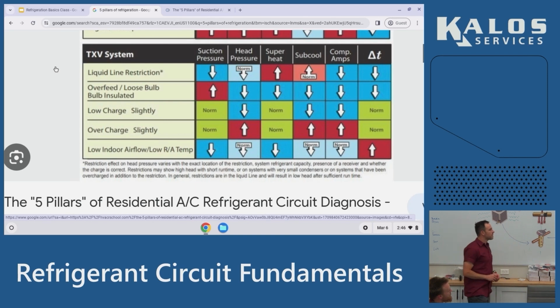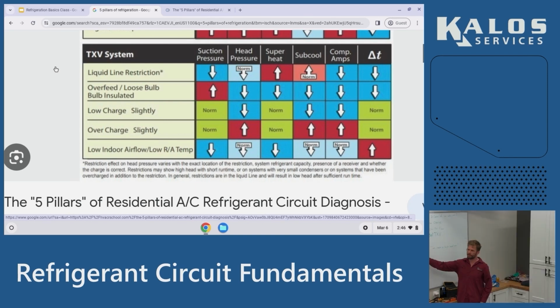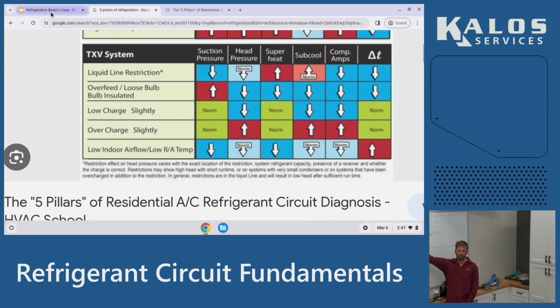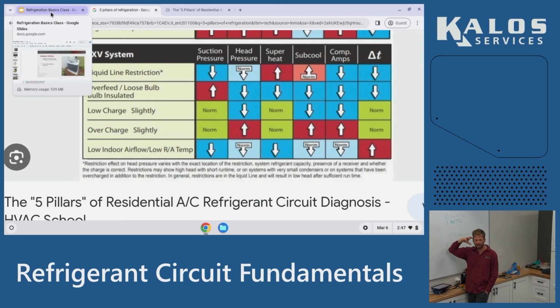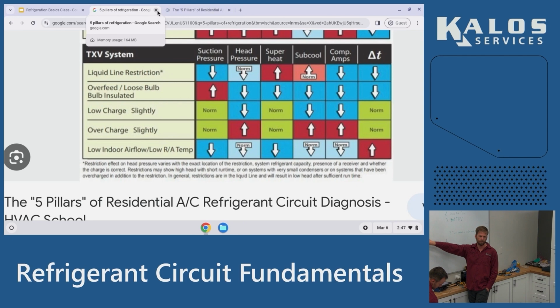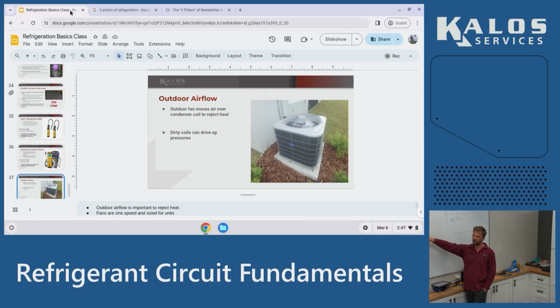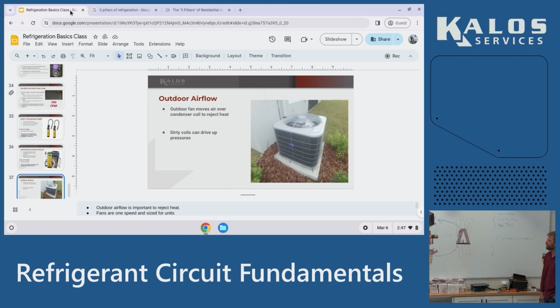Again, if you continue with revisiting the fundamental knowledge, what goes on here, and connecting it to what you're seeing in the field, all of a sudden, without having to do a lot of process without looking up a chart, you're gonna be able to put it together. You're gonna put a clamp on that suction line, it's gonna be cold. And then immediately you're gonna be like, okay, I know I'm not getting the heat load that my coil needs, but I know I'm getting plenty of refrigerant because it's cold. But I'm not picking up enough heat in the coil. Gotta start looking at airflow stuff. Yeah. And so the depth of your knowledge here really helps translate to diagnostic issues.